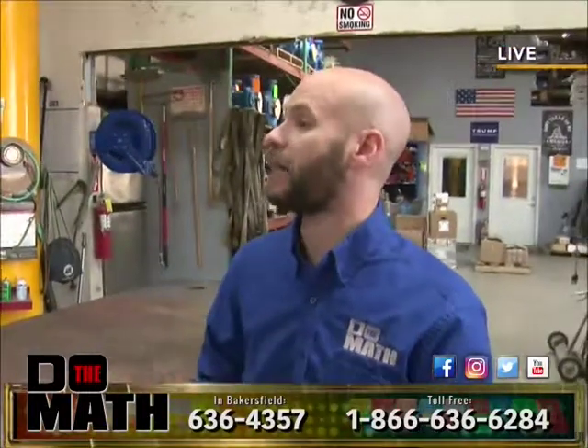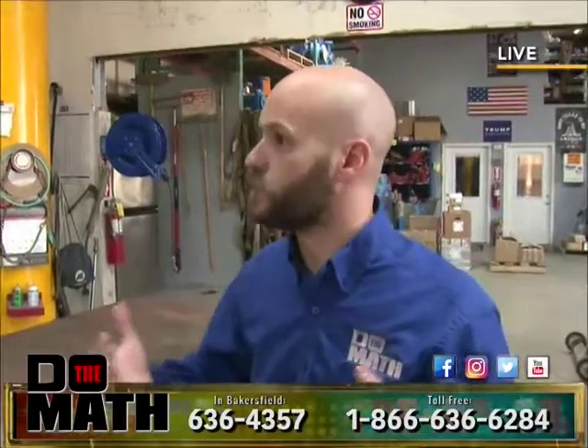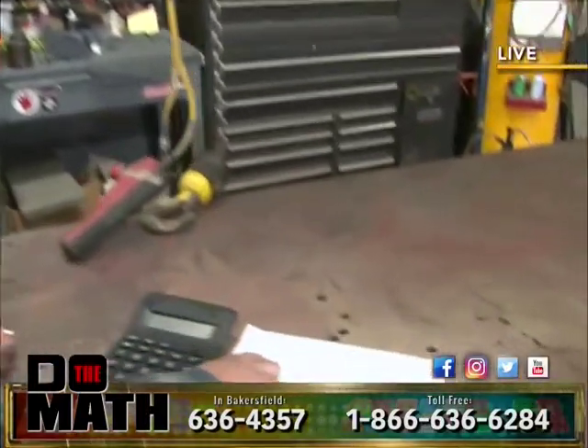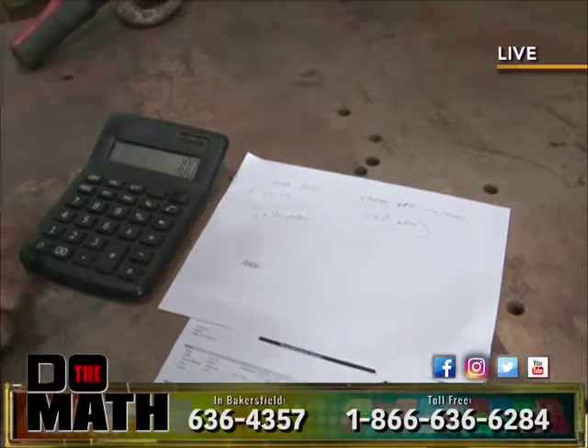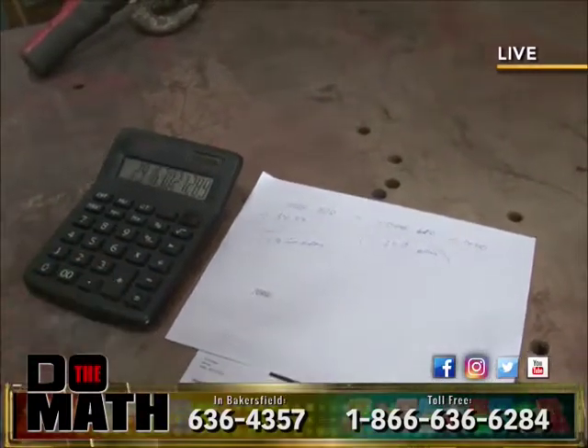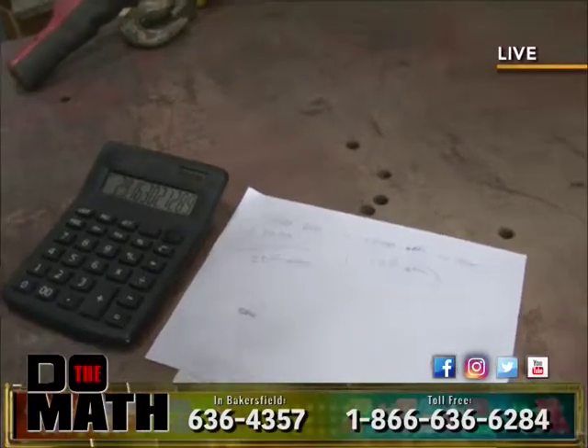For example, you would have a client that needed a unit that moved 1,000 barrels per day. You've got to get that to gallons per minute because of the work that you need to do with your manufacturers. Correct. So we utilize a conversion factor. We start with 1,000 barrels a day divided by 34.29, so we know our pump needs to do 29.16 gallons per minute.